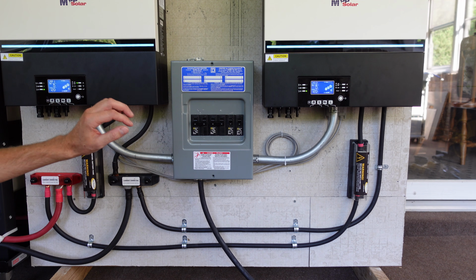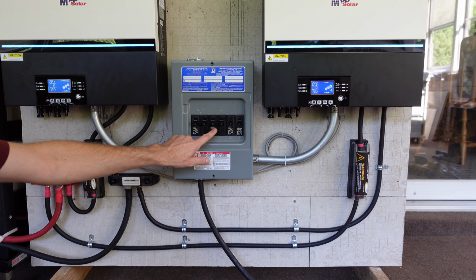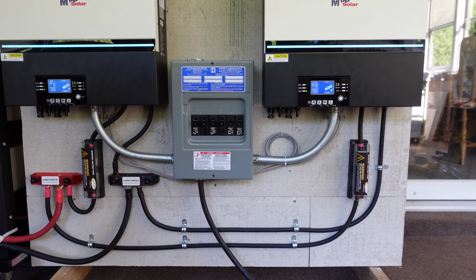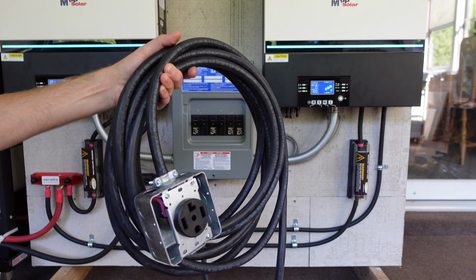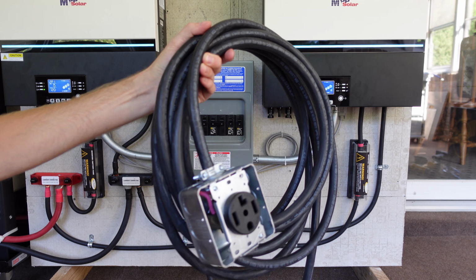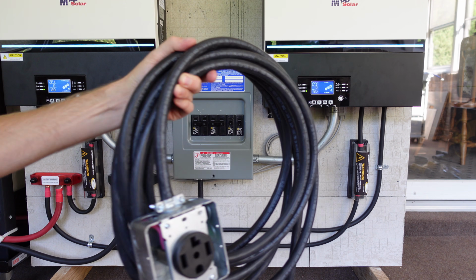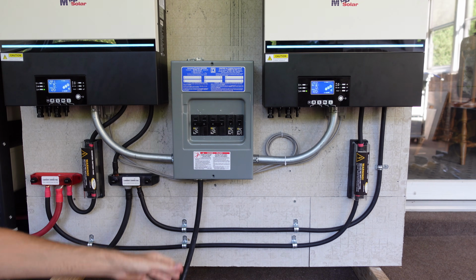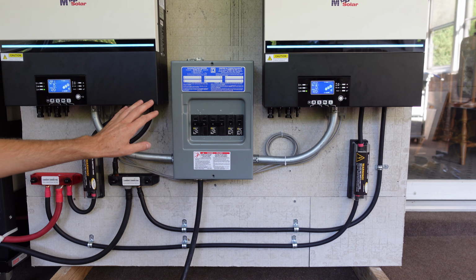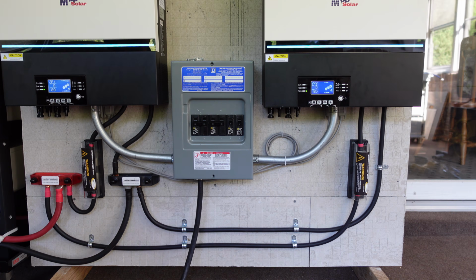And for a load on these inverters, I have a 30 amp double pole breaker in the middle, and I've got some 10-4 cable, some flexible cord here. Gonna run over to my clothes dryer, and that should put approximately a 5,500 watt load. So yeah, it will be interesting to see here how that works.